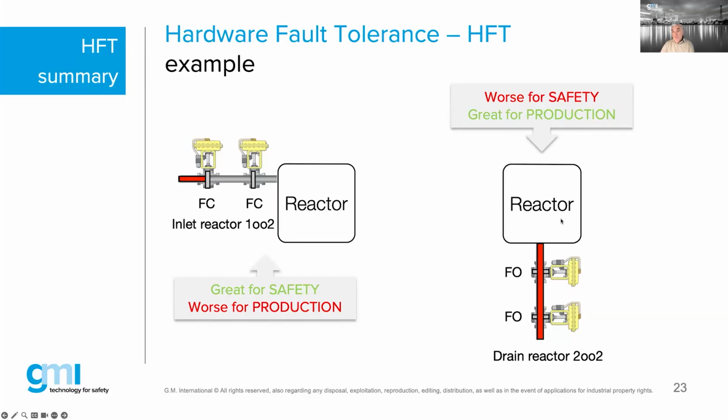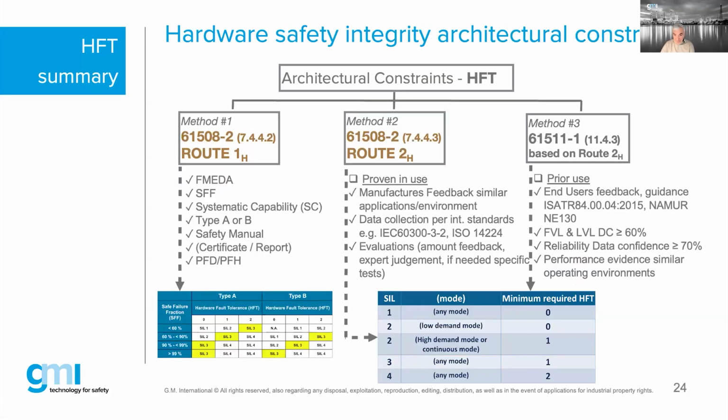So again, this is the worst scenario for safety, this 2 out of 2, but it's the best solution for production. Opposite, this is the worst scenario for production, but it's the best deal for safety. And somehow we will have to combine those two.